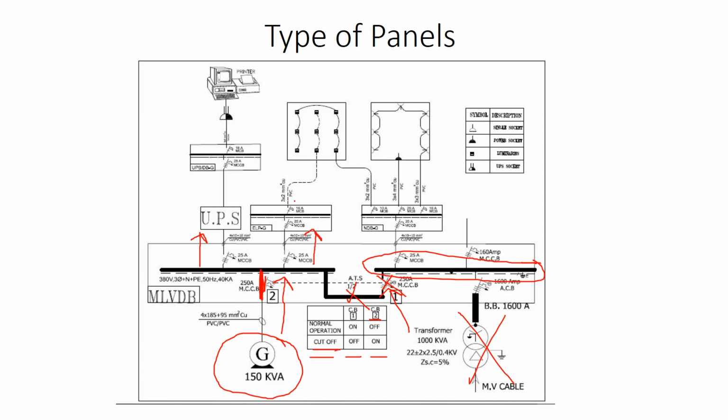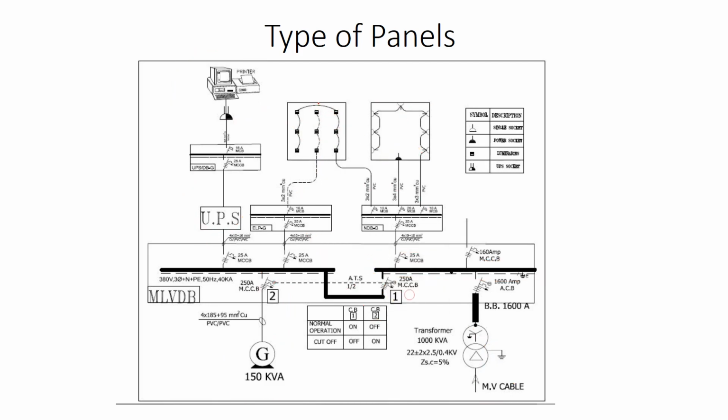So we will have electrical power to the 3 emergency luminaires, as you can see here. At the same time we supply electrical power to the UPS to keep it charging, and the UPS will keep supplying power to this critical equipment. This is the emergency state. As you can see, all of these luminaires are out, with no electrical power, except those three.